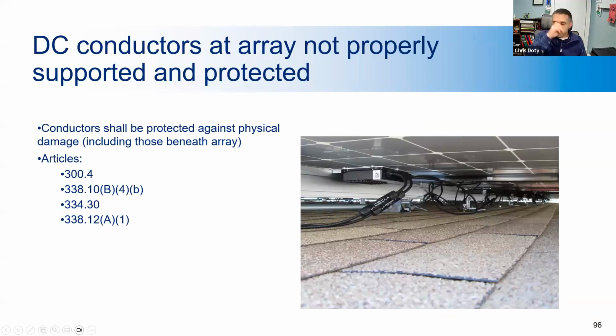Here we have one of the most common installation errors that you would see, on a rooftop where the conductors are not properly supported and are just laying on the roof where they're subject to damage by wind, snow, ice, movement, and especially the abrasive shingles they're in contact with, right? Eventually, wind will move them around enough that it will erode the insulation on the wires, and then you have a potentially dangerous situation and probably system failure.